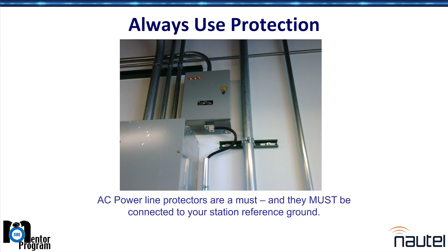So you need the surge protector because of the issue with transmitter sites. Almost 100% of the time they're built wrong, because the power comes in from the road, we hang the big lightning rod in the back field, and then we put all the gear we don't want to blow up in between them.